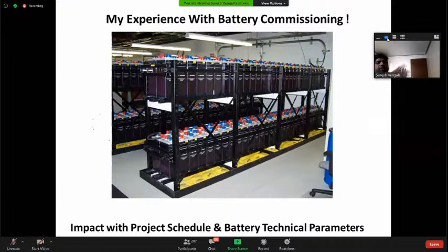To rectify this issue, I've seen projects use a battery monitoring system. Each individual battery is connected with a sensor, and all the sensors are connected to a module. From that module we connect to a computer with a special HMI, and we can view which battery is healthy through that system.